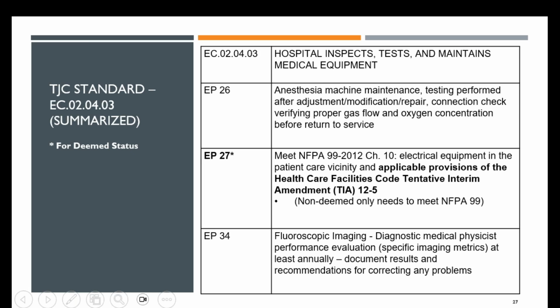And if you are deemed, you need to meet applicable provisions for the Healthcare Facilities Code, TIA 12-5, which relates to multiple outlet connections for our fun best friends, RPTs, relocatable power taps. We're going to get into RPTs a bit later. And finally, for fluoroscopy or fluoro equipment, also annually, a diagnostic medical physicist must conduct a performance evaluation following the specified metrics and documenting the results for correcting any issues.